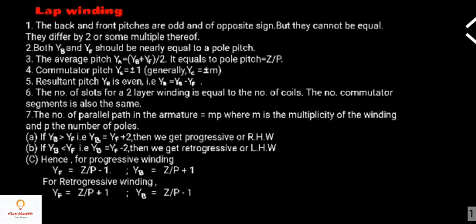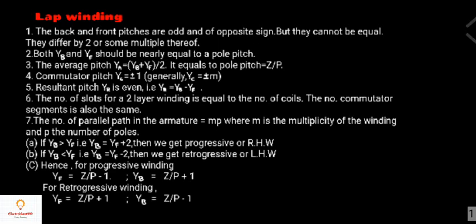There are some important points to keep in mind while doing a lap winding. The back pitch and the front pitch are odd and of opposite sign, but they cannot be equal — they differ by two or some multiple thereof. Both back pitch and front pitch should be nearly equal. The average pitch Ya equals back pitch plus front pitch divided by 2, which equals the pole pitch, given by the number of conductors per pole. Commutator pitch Yc equals plus or minus 1, and generally commutator pitch equals plus or minus m.